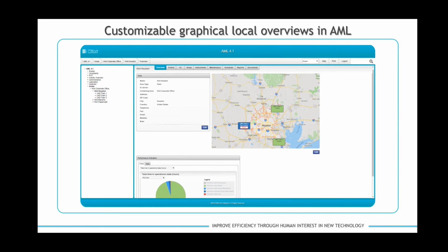So from the top level, you can immediately see for your entire plant if there is a fault alarm, a fault state, or some alarms. You can see if maintenance is being done, and you can immediately see if the entire area is being utilized without any problems. You can then click on these areas and it zooms into one level lower, and you can keep doing that until you find the area or instrument you're interested in. This way, you can do visual inspections to a certain degree within a couple of minutes, instead of having to go through the entire plant.